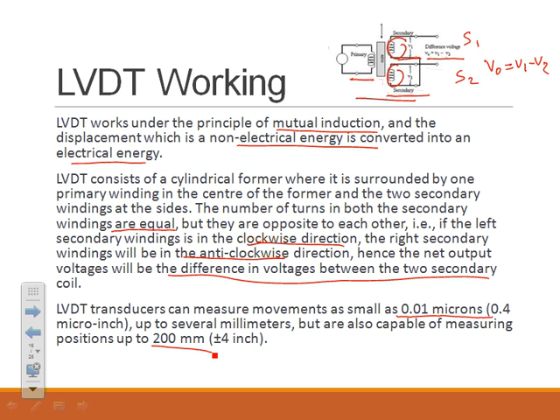LVDT transducers can measure movements as small as 0.01 microns up to several millimeters, but are also capable of measuring positions up to 200 millimeters, that is plus or minus 4 inches. This is the working principle behind the LVDT.